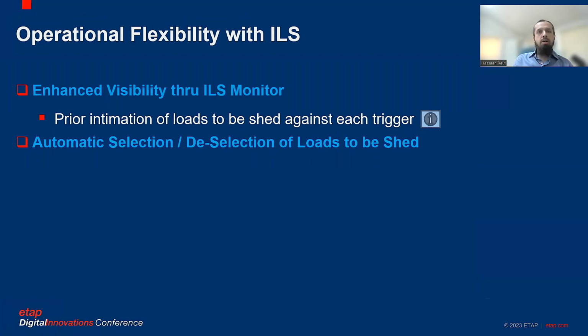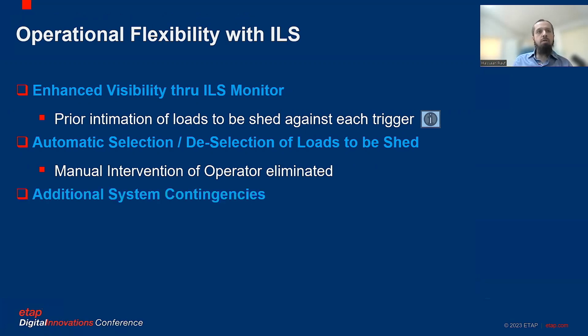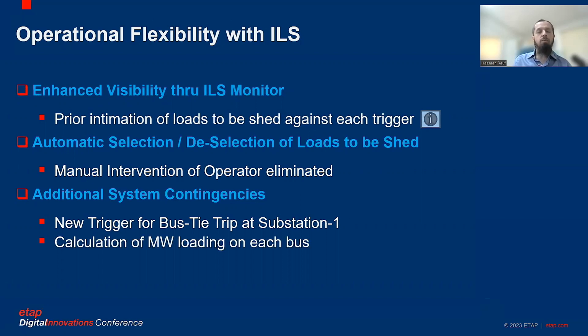Second was the automatic selection and deselection of loads. There was no operator intervention. The system would automatically select and deselect the loads against a trigger. Manual operator intervention was eliminated. Then we have some additional system contingencies which were configured, which were the bus tie trip and the bus loading. Again, this was not available in the old system. Using the real-time data and the analysis and calculations of the ILS, we were able to calculate the megawatt loading on each of the main buses at substation 1. And thus, the operator has increased visibility of the system as well.